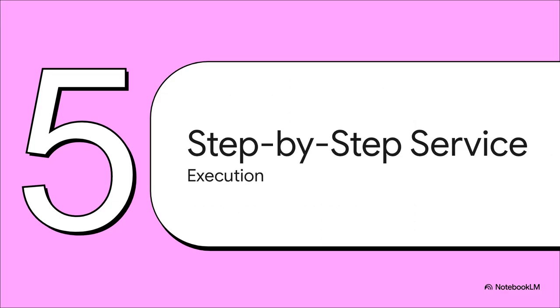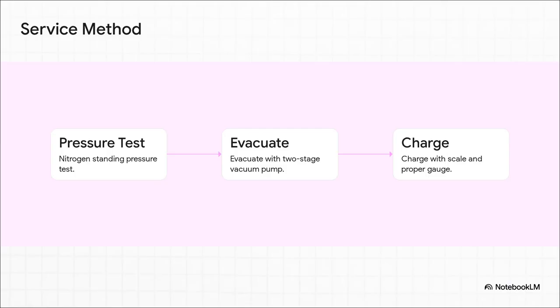Section 5. The step-by-step service method. Time for execution. Okay, let's break down the actual process. Before you even think about opening a refrigerant circuit, you must perform a standing pressure test. You do this using an oxygen-free dry nitrogen cylinder to safely track down leaks without releasing any refrigerants. Once that's fixed, you evacuate the system safely using a 2-stage vacuum pump, bringing it down to a deep vacuum. And only then do you proceed to precisely charge the system using your digital scale.